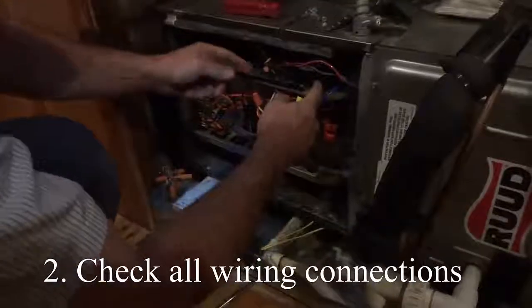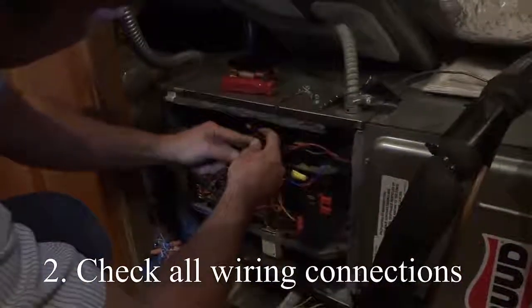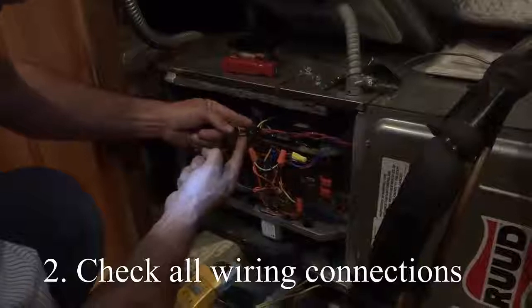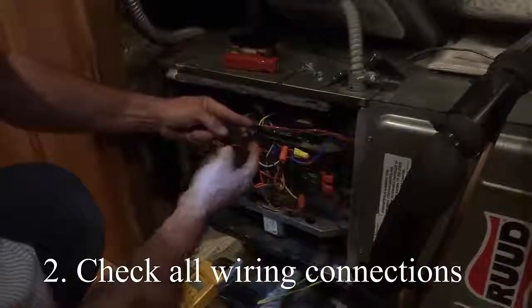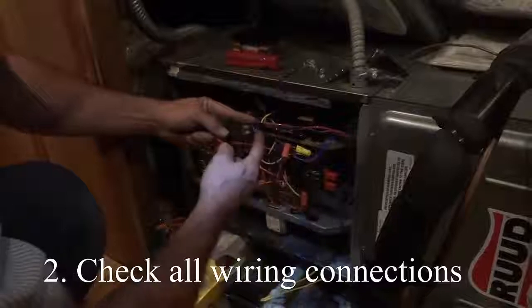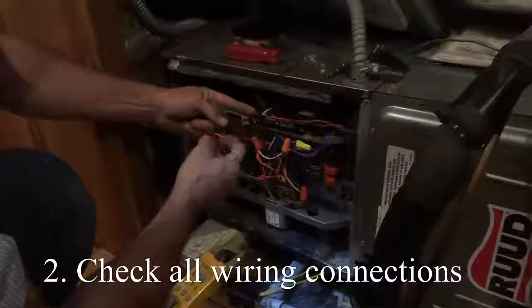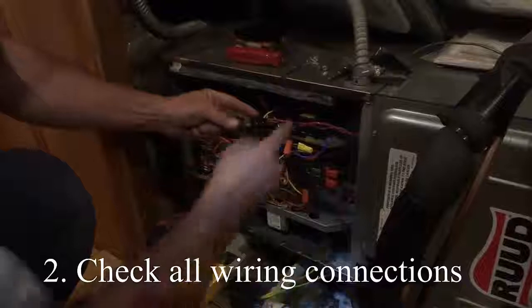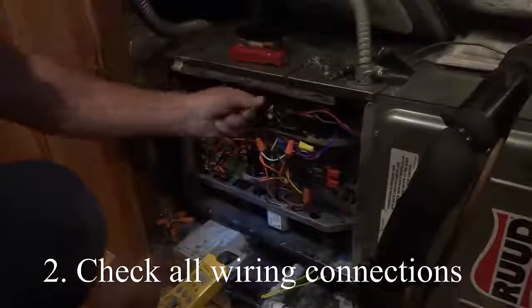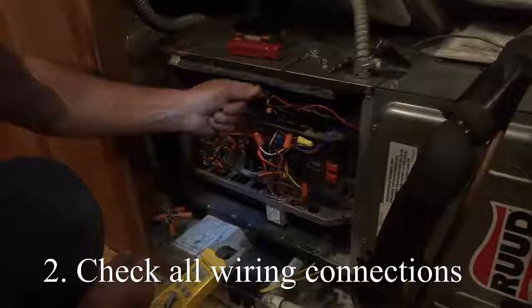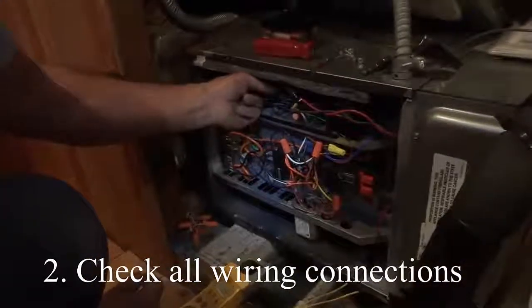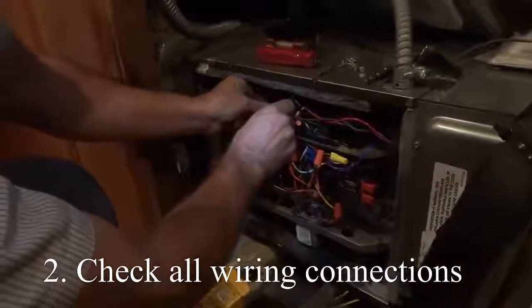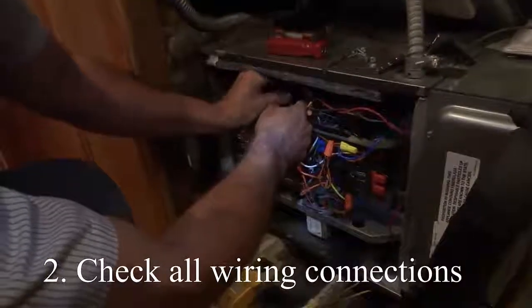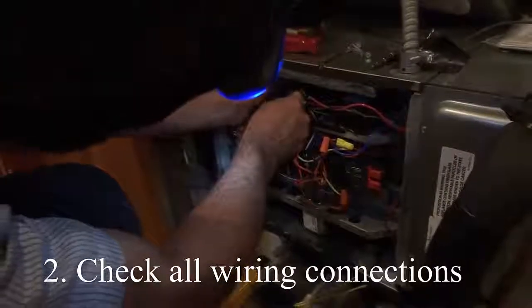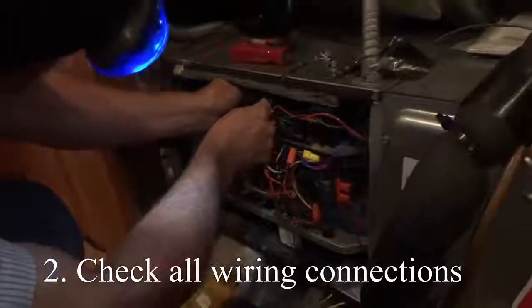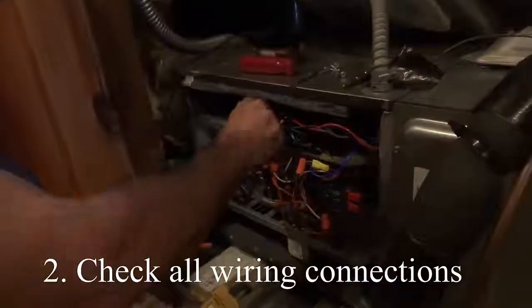This transformer's been replaced at one point in time, and they've added this fuse in here to not pop this transformer in the future. If you get a low voltage short, it'll just pop this little car fuse here instead of popping that. So that's a good deal to have in there, so you don't have a costly repair in the future if you have a short on your low voltage. All the connections are tight.